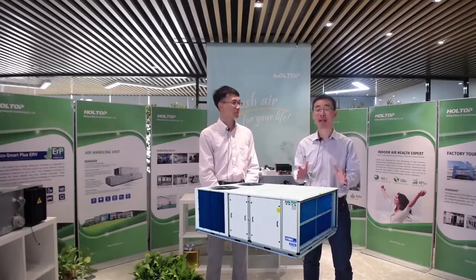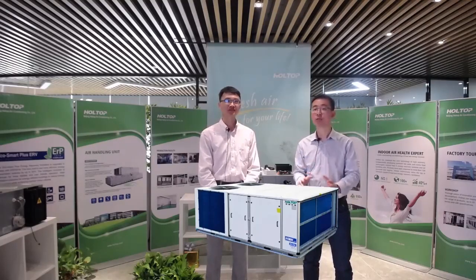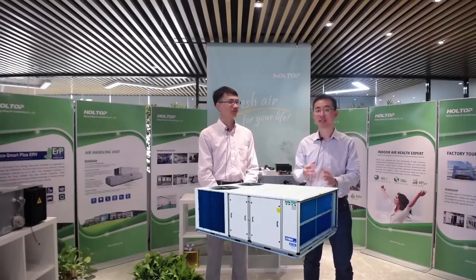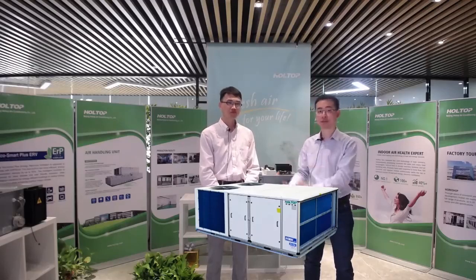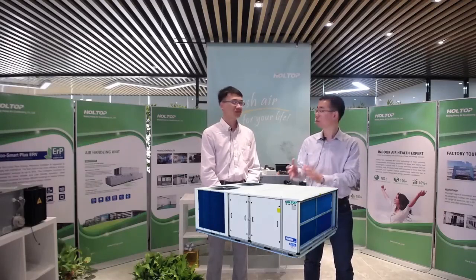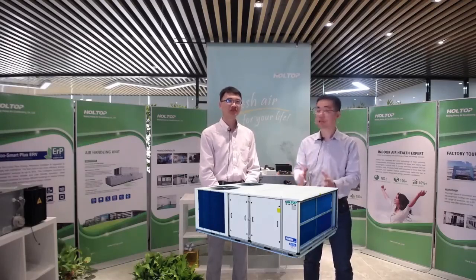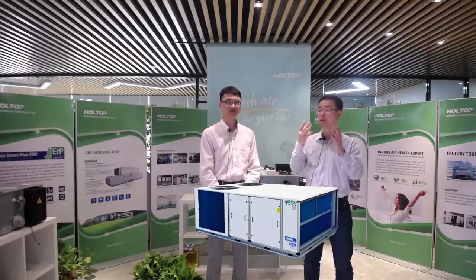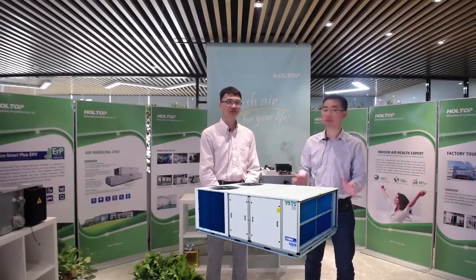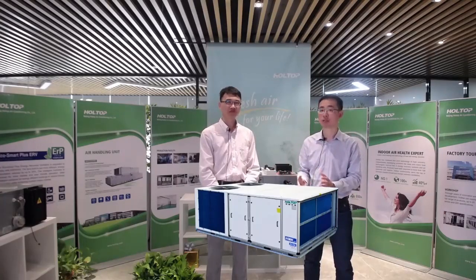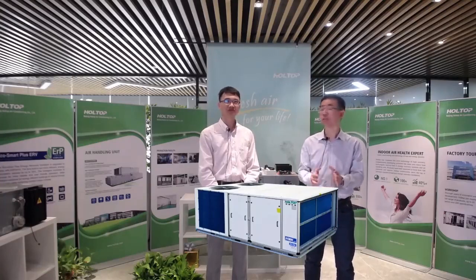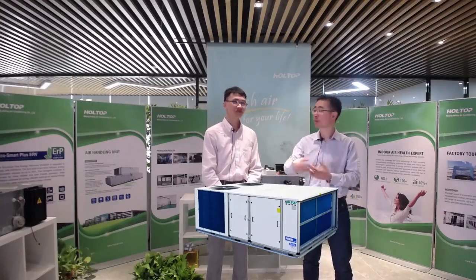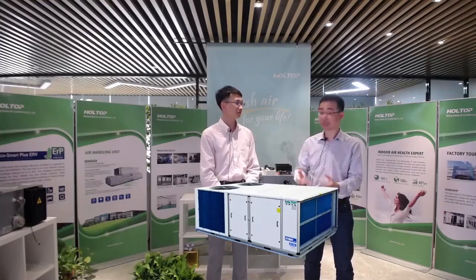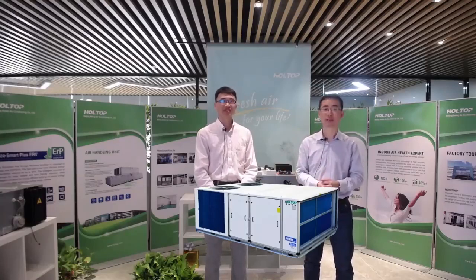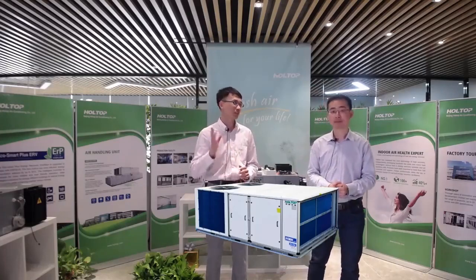The unit adopts a compact design concept, integrating indoor units and outdoor units, so there is no additional refrigerant pipe connection and welding job at the project site. It is safe and easy to deliver and install. Package units could be placed outdoors on the ground or on the rooftop. No machine room or outdoor space is required for housing the packaged unit. Only a few works are needed: power cable connection, control wiring connection, and the ducting connection. That is all. I believe that it is a very attractive point for our customers.